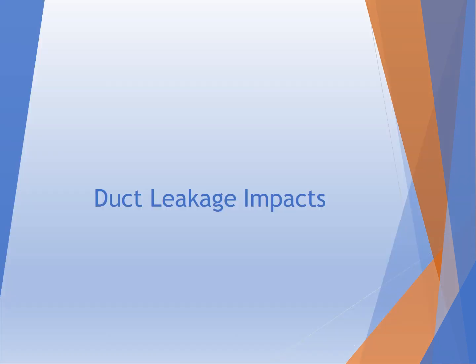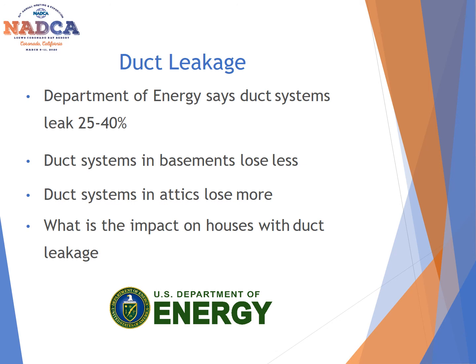Over the next couple slides, we're going to look at how duct leakage impacts the overall indoor environment. A lot of what we're going to talk about in the next few minutes is going to be about duct leakage. Starting off, just a few statistics for you. The U.S. Department of Energy basically states that, in general, ducts are going to leak. They are built with the knowledge that they're going to leak. The problem is, with older ducts, it's not uncommon for them to leak 25 to 40% total. That means 25 to 40% of the air going through the ductwork is not making it to the register. It's leaking out through other areas within the system. Duct systems in basements lose less, it turns out, and duct systems located in attics lose more air. So what is the impact on these houses when you have this much duct leakage and you're blowing air into other spaces other than where you actually want the air to flow?